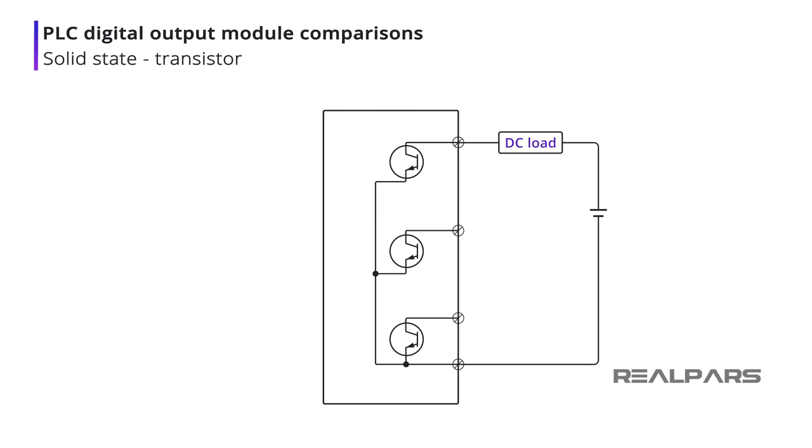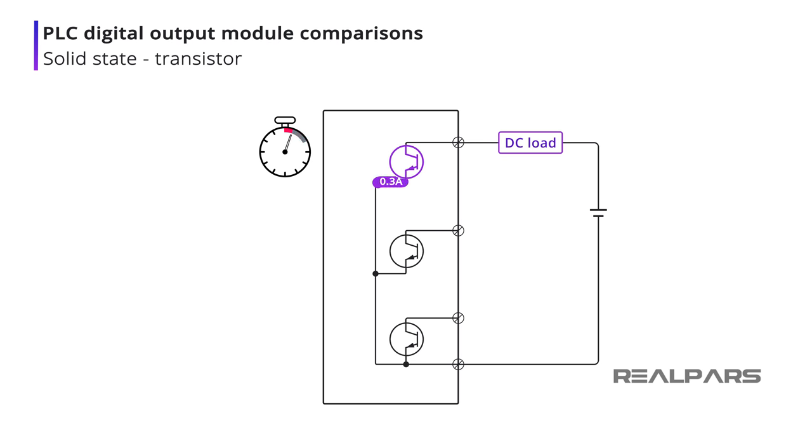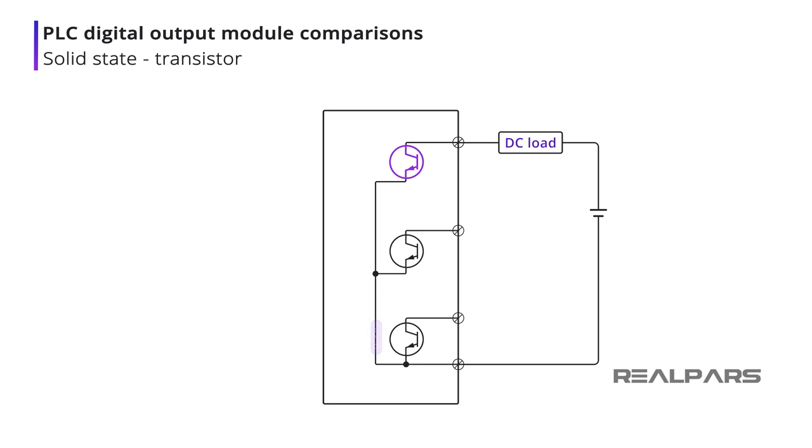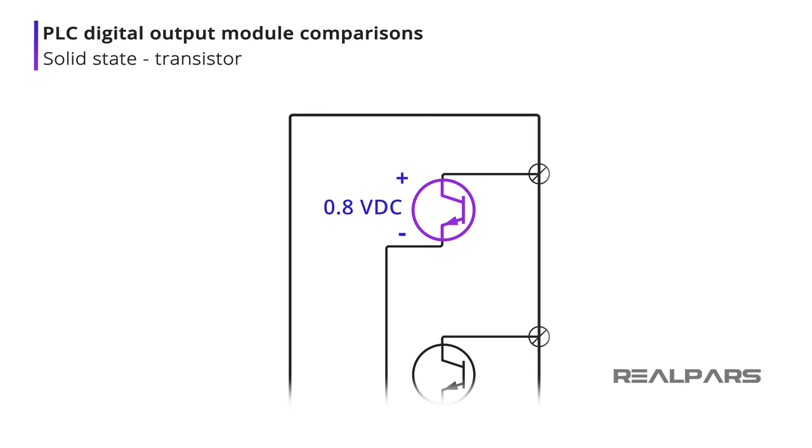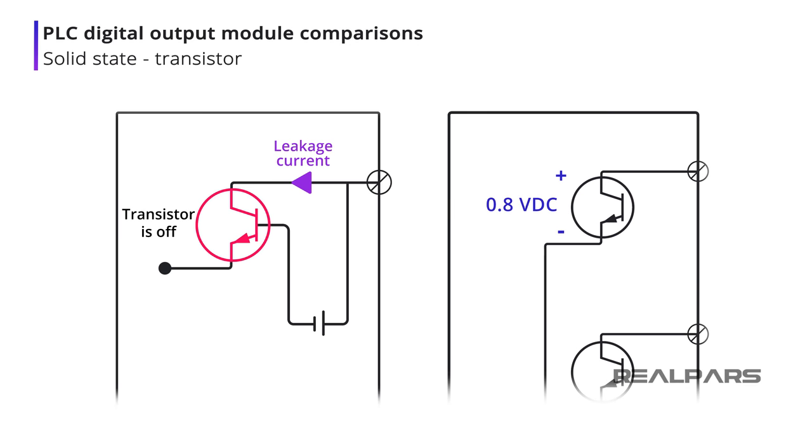Transistor output modules are for DC applications only. Transistors typically cannot switch a large load current, as can a relay. A transistor is fast because there are no mechanical parts. Their response time is much faster than relays. Because a transistor is not a perfect switch, there is always a small voltage drop across it when turned on. In some transistor modules, there is a leakage current even when turned off.